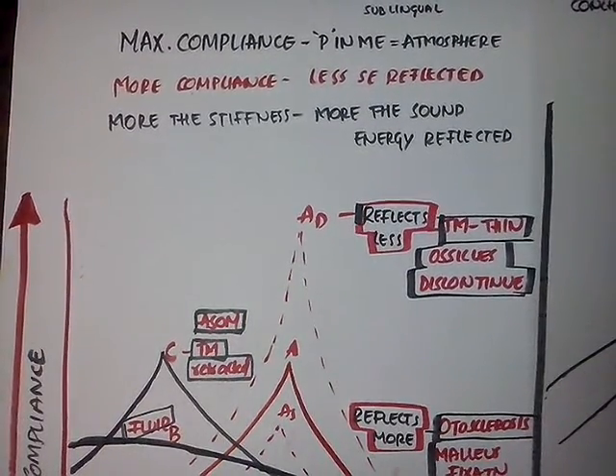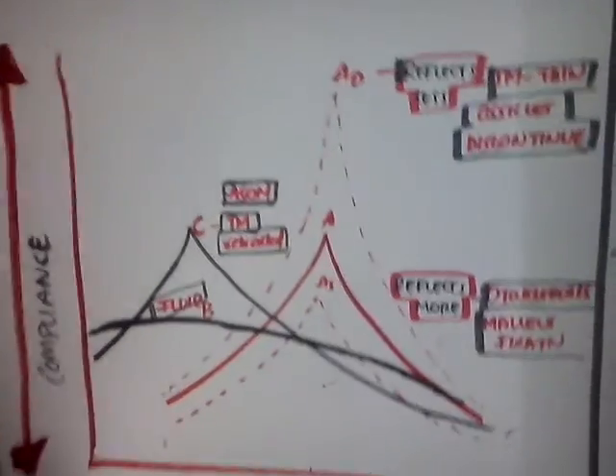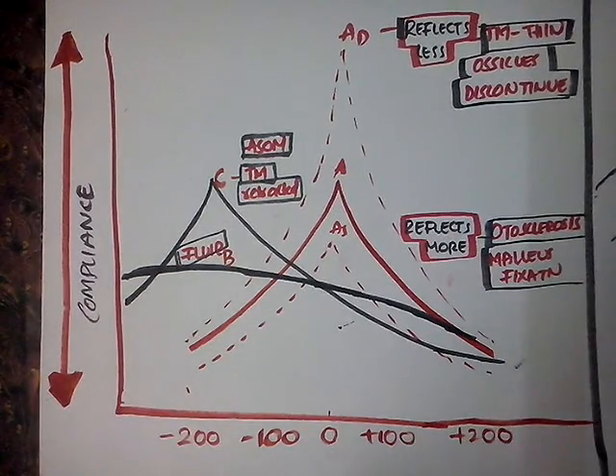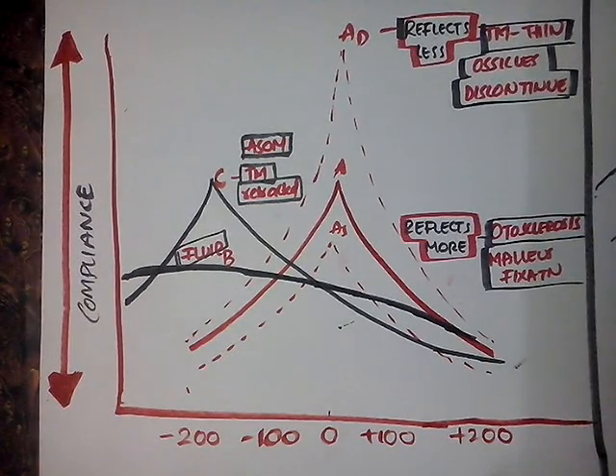Compliance is nothing but the elastic nature or the flexibility of the tympanic membrane. More the compliance, less sound energy is reflected. For performing this technique, we need an equipment that is a probe with three openings: one for generating sound, one for generating pressure, and one for picking up the sound energy reflected.